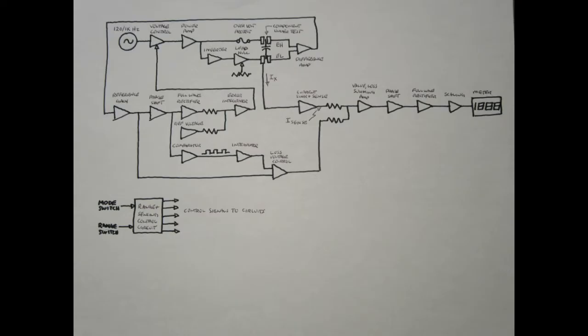I'm going to talk now about the basic circuit theory of this digital LC bridge. Pure capacitance and pure inductance are pretty easy to measure, but in the real world with real components, we find that along with the capacitance and inductance, there's always some resistance and other kinds of losses, and taken together they add up to the impedance of the component. The trick to getting a good capacitance or inductance measurement is to first measure the complex impedance, and then remove anything other than the actual capacitive reactance or inductive reactance, and then convert the reactance to a scaled capacitance or inductance value.